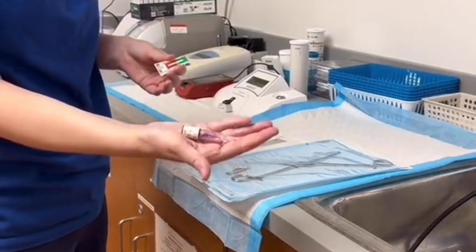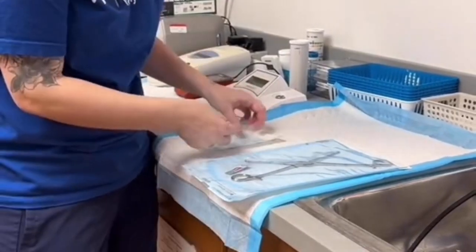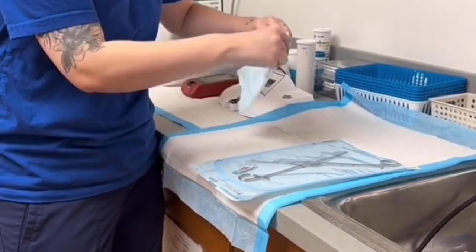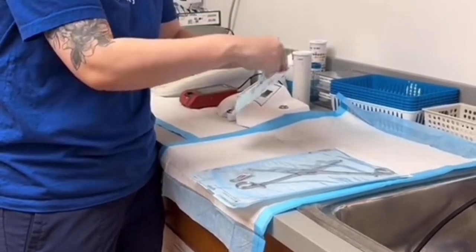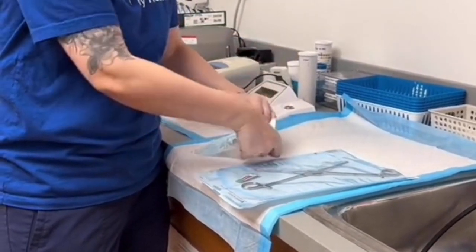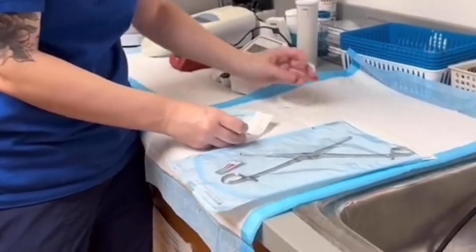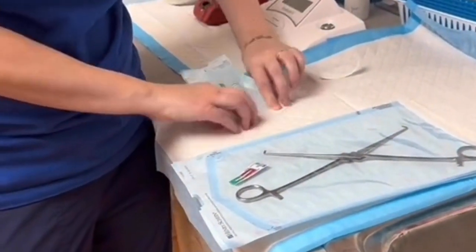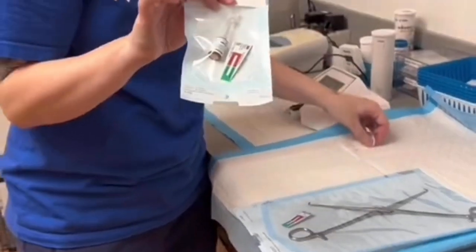During the first cycle of the day, use a process challenge device by sterilizing a biological indicator and a chemical indicator. If any indicator doesn't pass, treat all instruments in the load as not sterile and repackage and repeat the process.